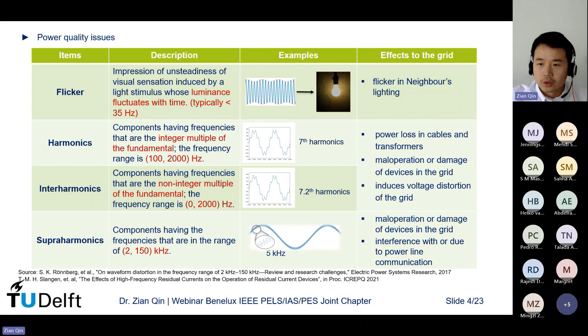Okay, when we talk about power quality issues, some people may say we try to minimize the power harmonics or flickers, or we try to optimize the harmonics. However, what you really need to do is not to minimize or optimize them. What you need to do is check the standard, and in the standard there is a certain limit stated. You just need to make sure that the harmonics are not beyond that limit, and that's it. Usually you don't want to put in more effort than that, because you get nothing, but you need to pay more because of the higher cost. So the only thing you need to do is check the standard and make sure the harmonics you inject into the grid are not beyond that limit.